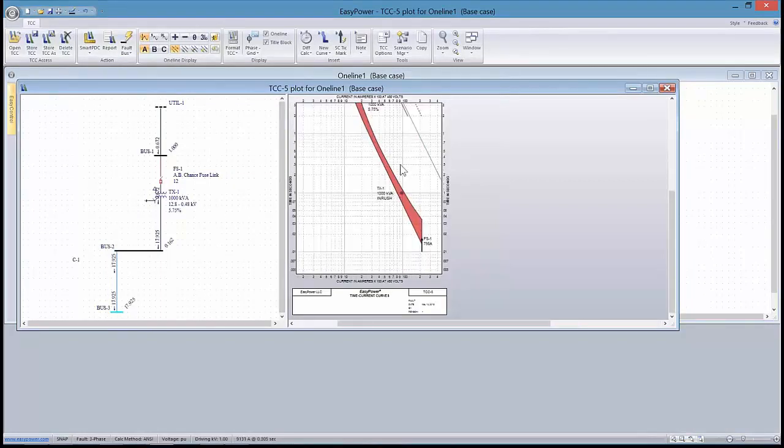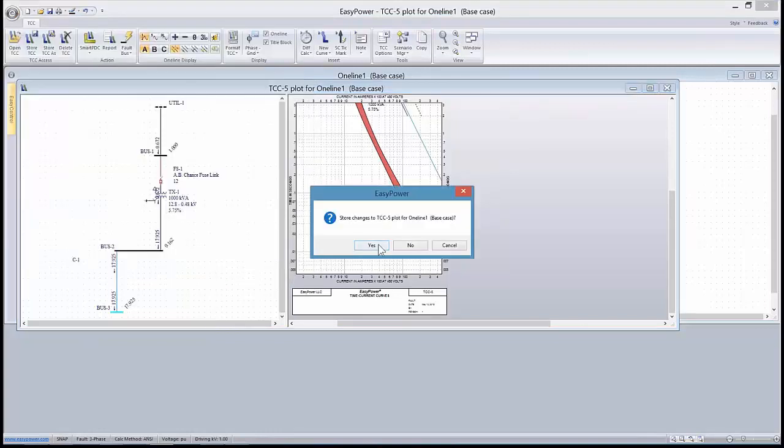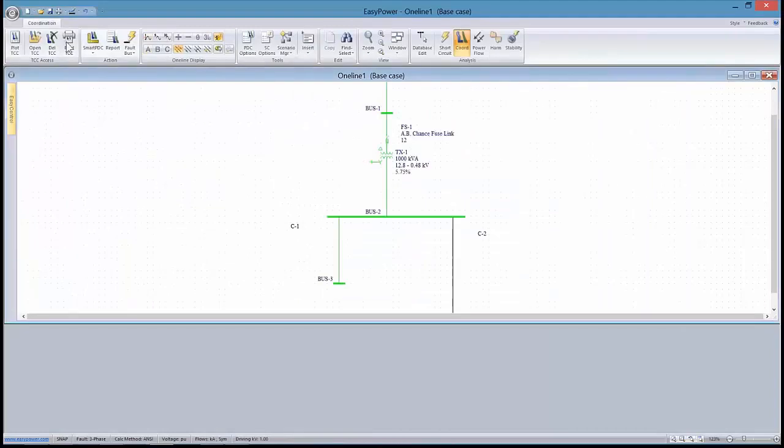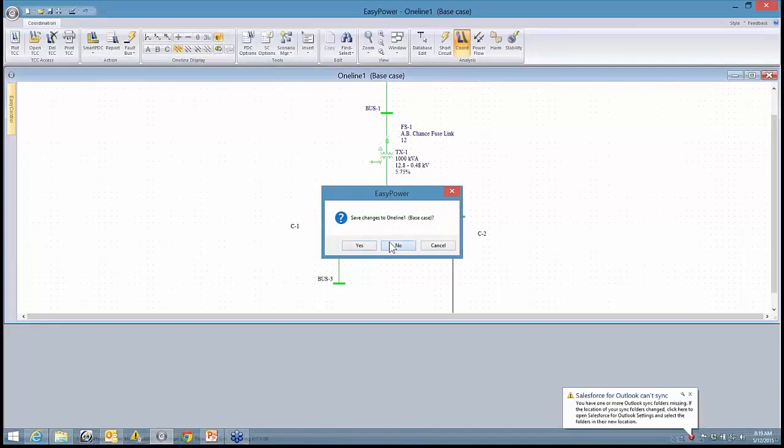Okay. I think I've kind of beat that one to death, but the significance here is time is critical in arc flash. The elements that control time are the protective devices, and so even in a very simplistic example like this, it's important to understand what the tool is doing for us and how to get the results out of it that are useful for a number of reasons.